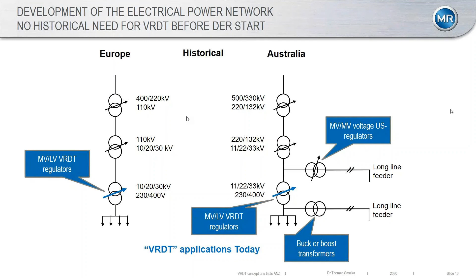We've seen a large debate about network operators trying to control DER and inverters in Europe. Some like that and do it; others say it's not their asset, so it's probably not the best idea to take care of directly, but they define in the grid code how these DER units shall comply and offer ancillary services, including reactive power flow into the network - not just active power, but reactive power too, to help with reactive power balance and voltage issues. So VRDT technologies and tap changers can now also replace MV regulators.